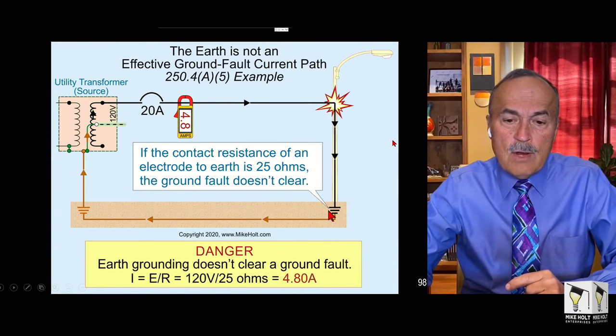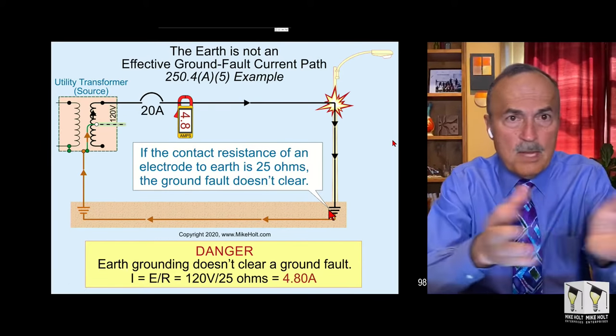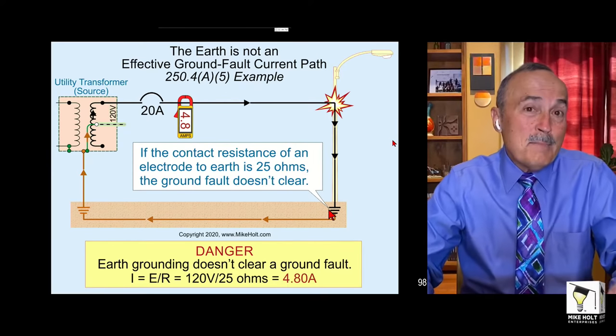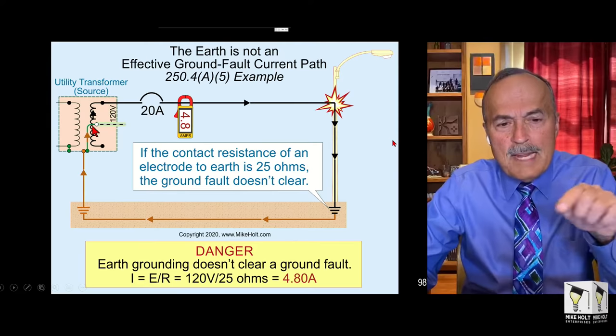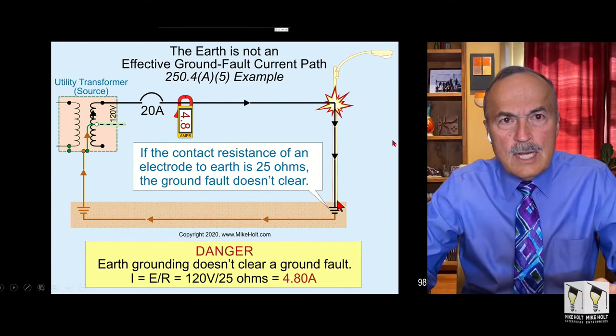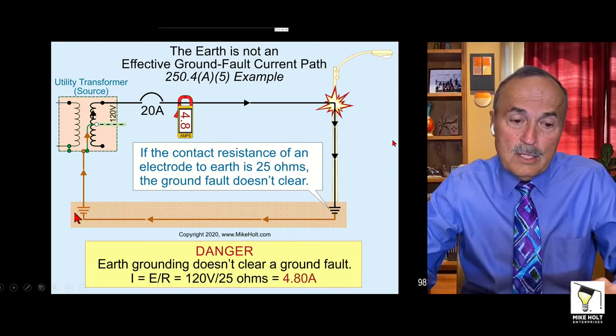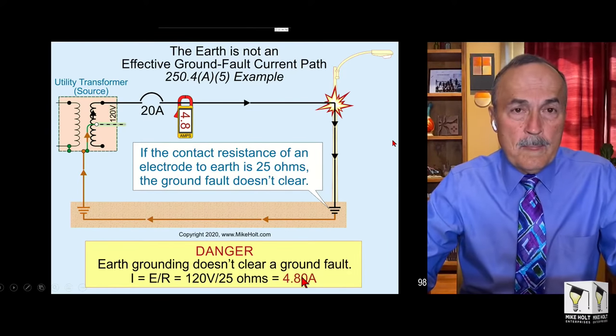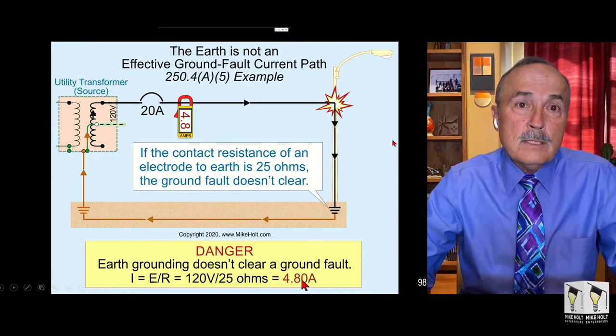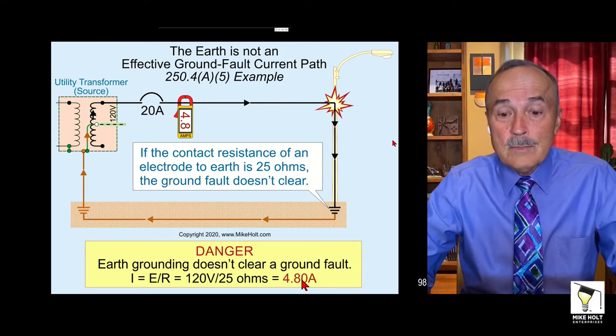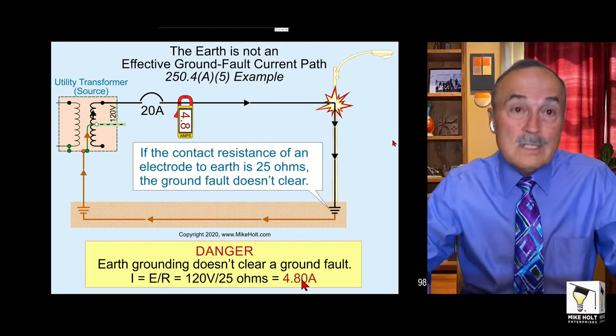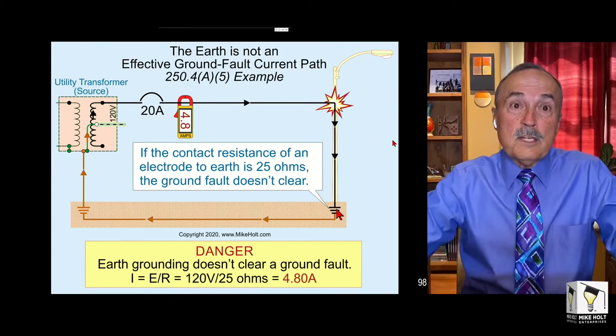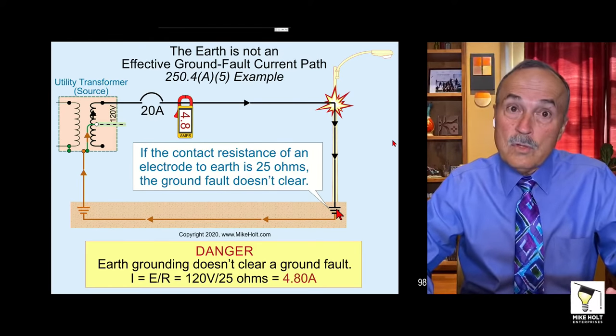If you drive a ground rod and that ground rod is 25 ohms contact resistance to the earth - we're measuring the contact resistance of that ground rod to the earth - how many amps would travel from the source, to the metal pole, energize the metal pole, go to the ground rod, and travel through the dirt to find a path back to the source? If that resistance is 25 ohms, Ohm's law gives you 4.8 amps. Guess what? It's not tripping a breaker. It's not supposed to. What's not okay is thinking you can use the earth as an effective ground fault current path. If you're driving ground rods because you're worried, you probably don't know about the effective ground fault current path.